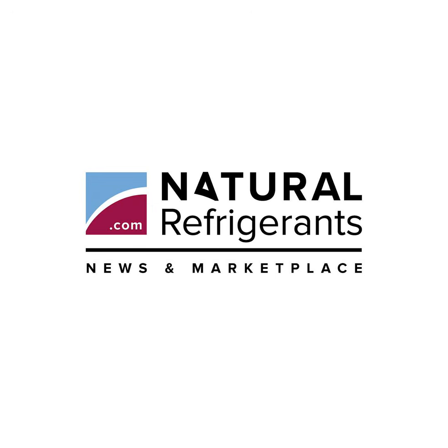Configuration options. Macalusco highlighted 2 additional projects that demonstrate solution flexibility. In a retrofit of a 700-unit apartment building in Washington, D.C., Lync installed 5 Aegis A500 units with cool water recovery beneath the building's chiller plant, along with 5 custom storage tanks and an electric circulation tank. We can fit it in a very tight space, increase the performance of the mechanical cooling system, and provide hot water to the apartment complex, Macalusco said.